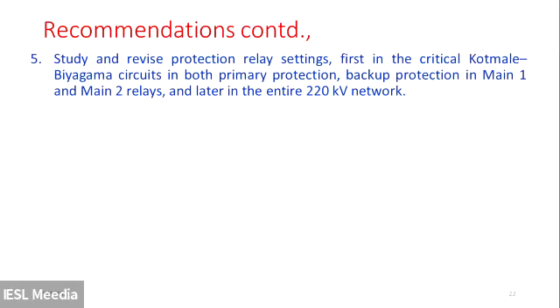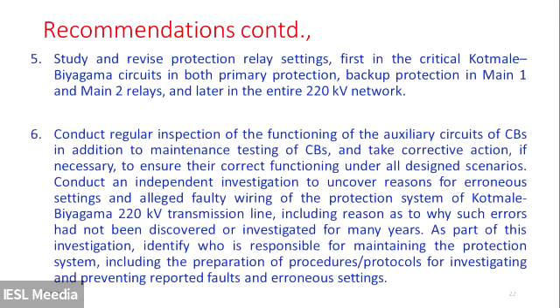And then we also found that there were some ambiguities. One was reset settings, definite time versus instantaneous. Likewise, we found that some of the overcurrent settings were contradictory at the 2 ends of the line, which is not possible. So we wanted to have a revision on that. And also we recommend to conduct regular inspection of the functioning of the auxiliary circuits of CB circuit breakers, because in the end fault operation, when the committee made several requests, the CEB also, I think, had their own investigations anyway, and they found that the implementation of the relay logic had problems. Because in the documentation, what we found is a normally closed series connected auxiliary connection, whereas what existed was a normally open parallel connected logic implementation, and they were also not identical on circuit 1 and circuit 2. So that is somewhat questionable.